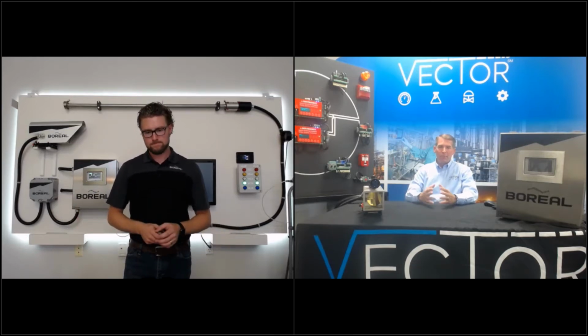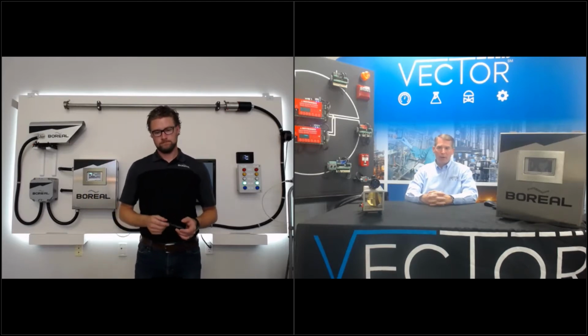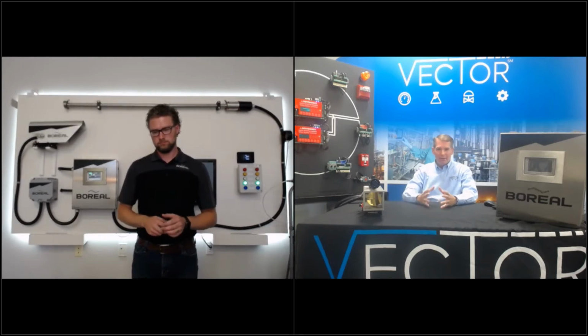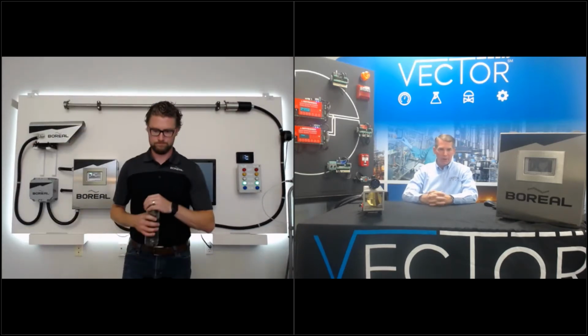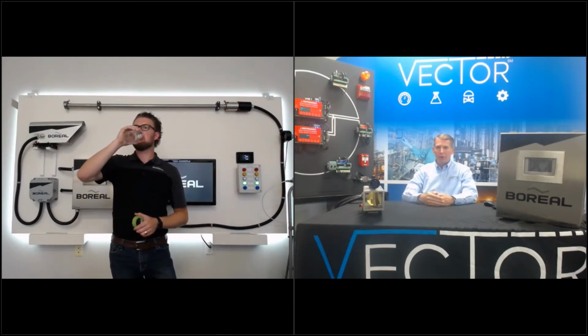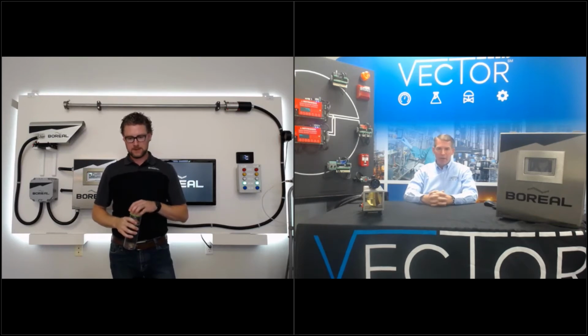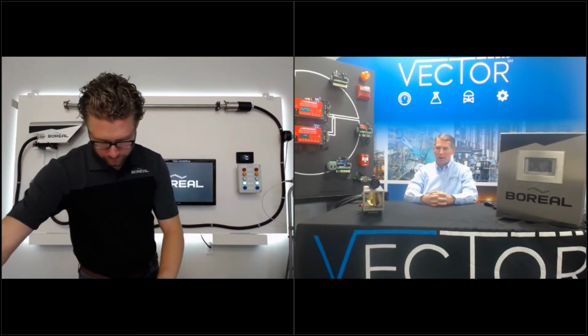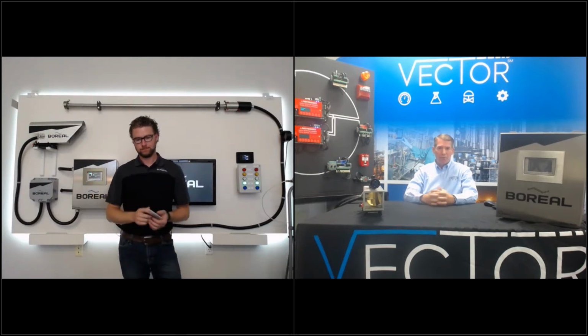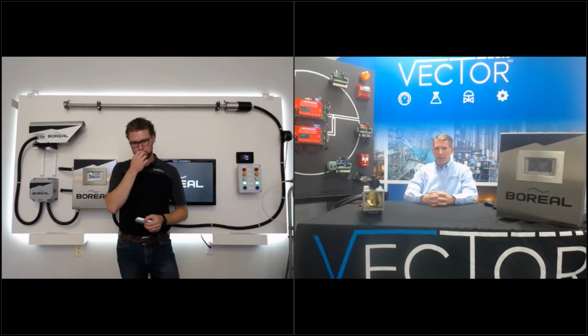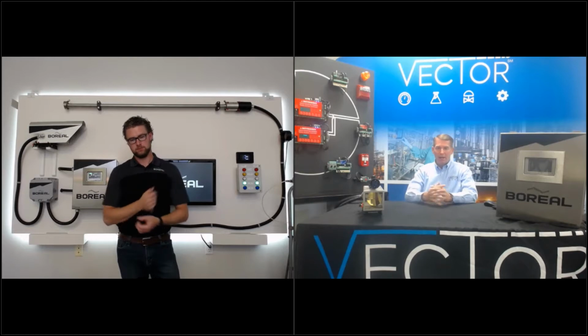Right, Kyle, and one thing you did mention was speed of response. One thing I want to point out is that these laser gas detectors are active, fail-safe gas detectors. They never go into a sleep mode. Kyle said they're looking for a measurement every second. They do not go into a sleep mode, so they're extremely quick to respond, which is important for a safety system. There are some systems or equipment out there that go into a sleep mode to conserve power or a battery, and that can lead to a much longer time for you to recognize that there is a gas leak. This type of unit will not do that. And if for any reason it cannot see or read gas, it will let you know by indicating a fault.